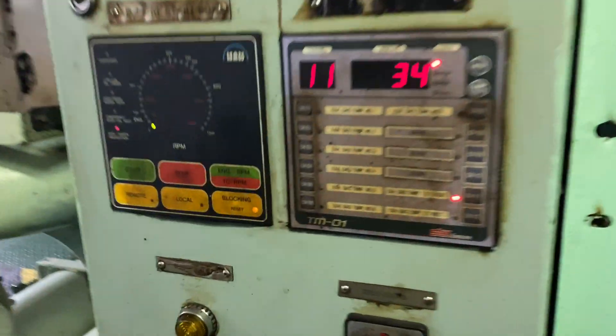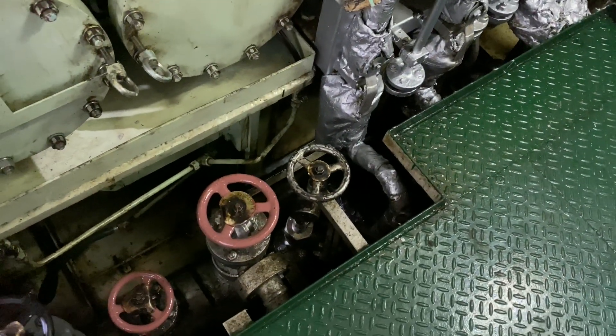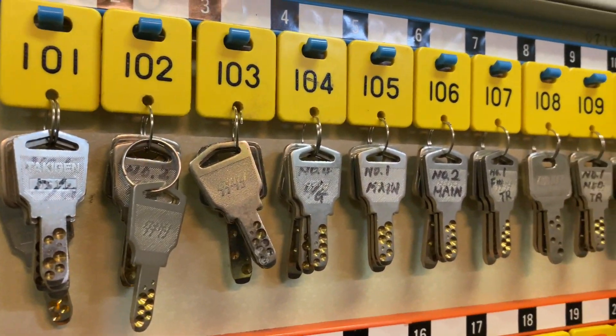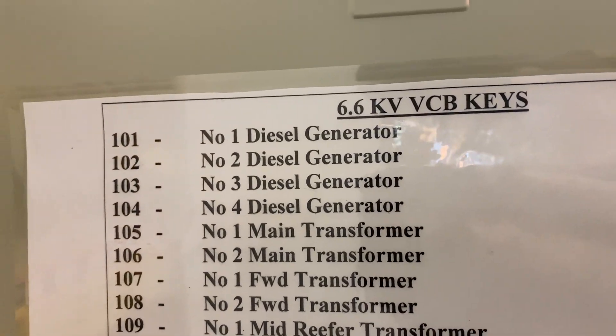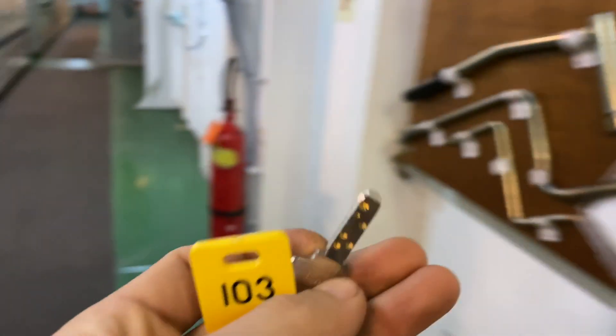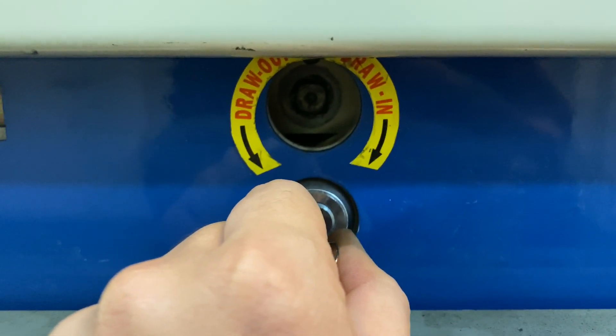After doing the permit to work, we need to block the operation of the generator so that it will not start automatically. The key is here and you just need to check which is the right key. For DG3, it is key 103. Key 103 will be the one inserted here so that we can start racking out the VCB.